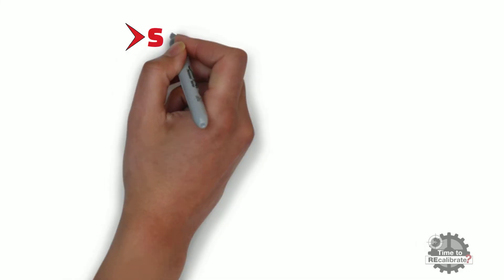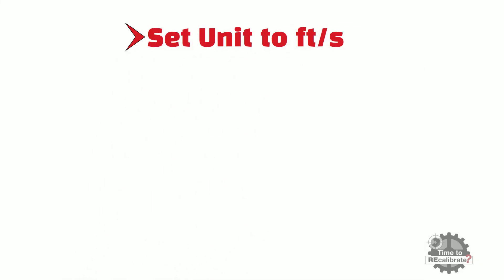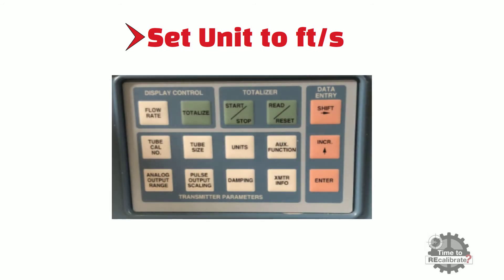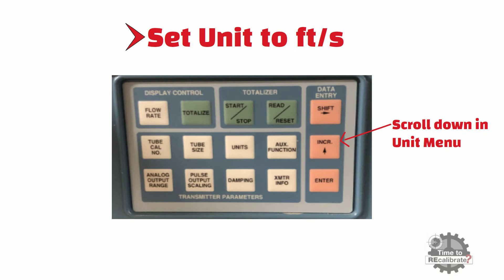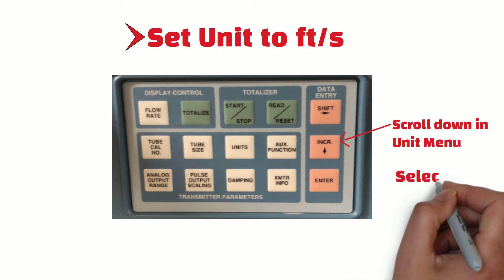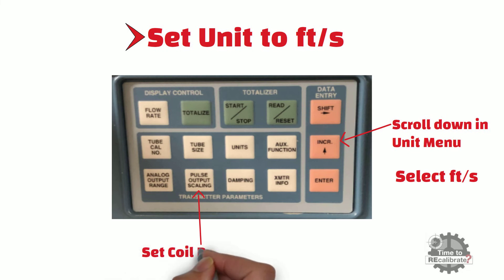Step 4: Set the unit to feet per second. Press the unit button to enter the unit menu, then press scroll down. All different types of flow measurement units can be found in this menu. Select feet per second and press enter to store this unit in the transmitter. Repeat the same steps to set the coil pulse mode to 5 Hz.